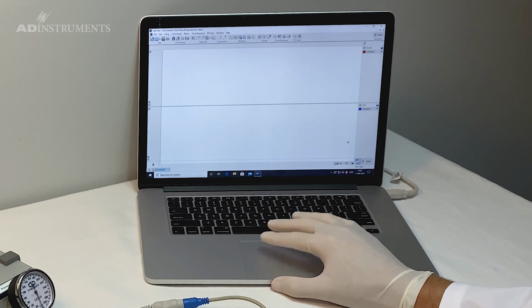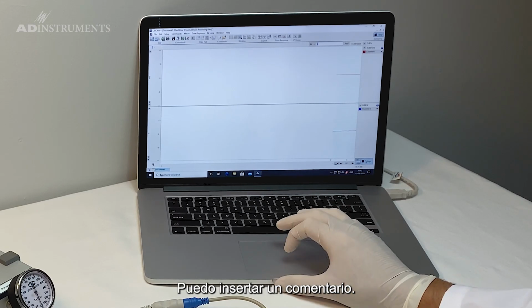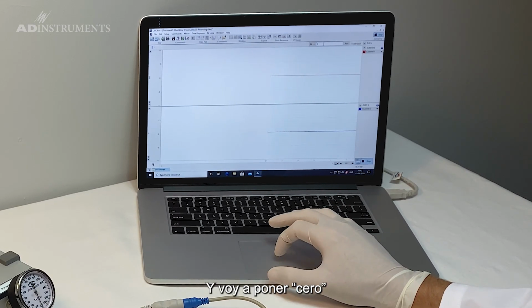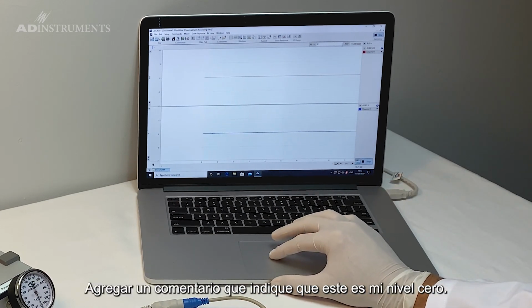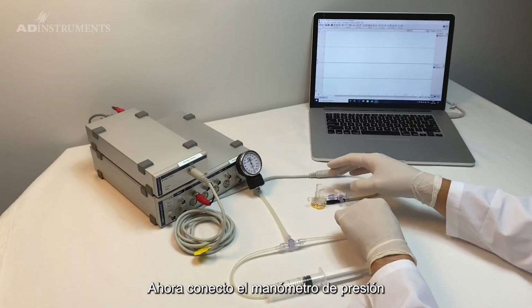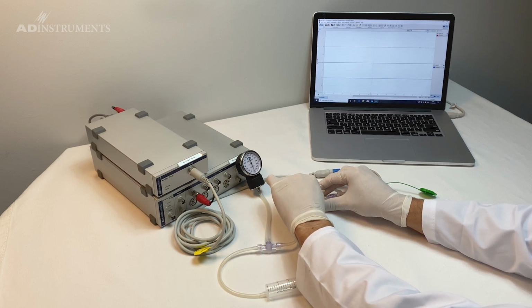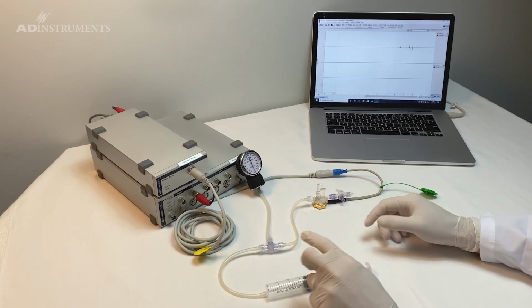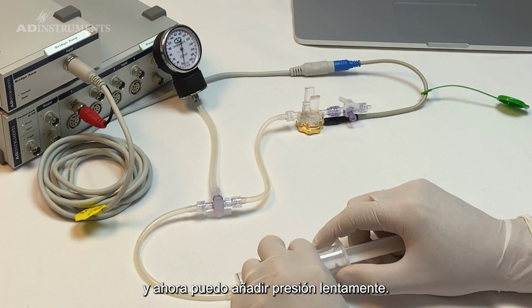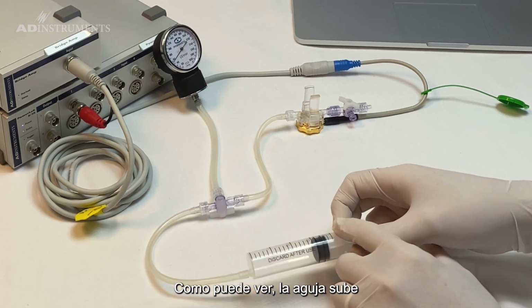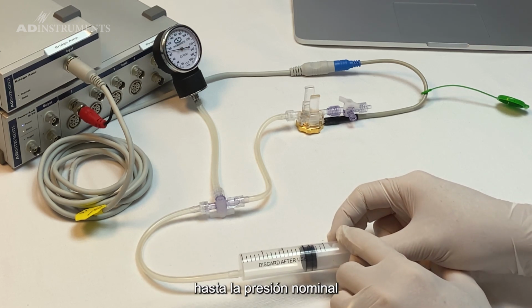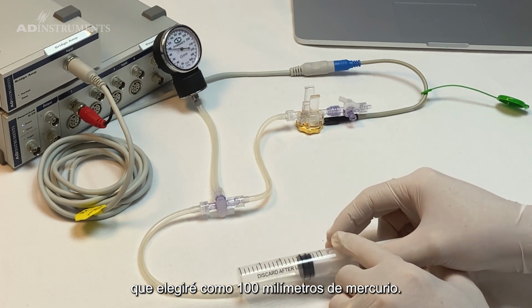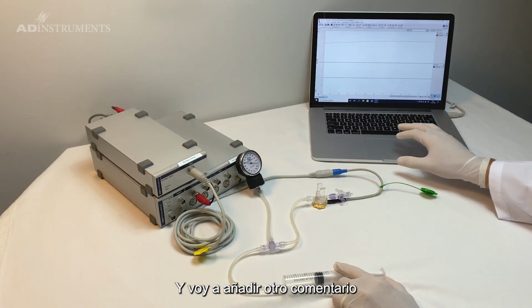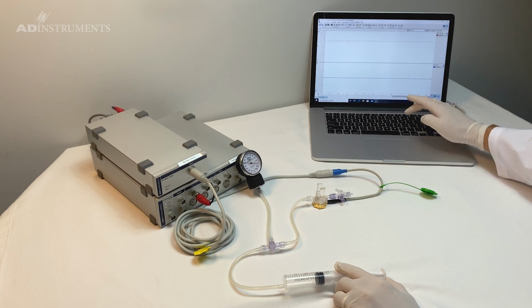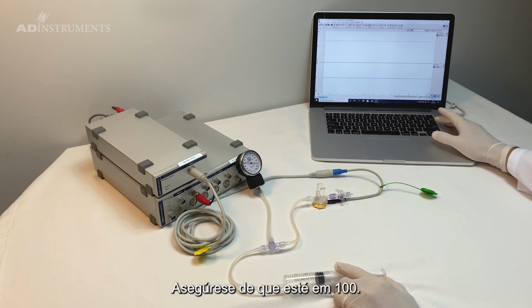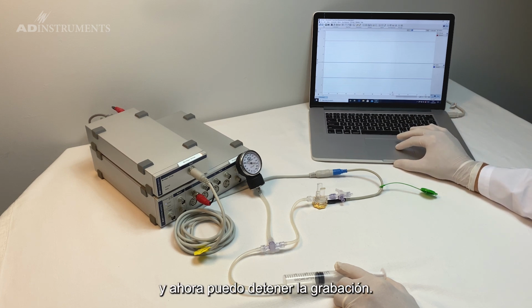So I can start recording, and because it's zeroed and open to air, I can now drop a comment, and I've put in 0, drop in a comment that this is my 0 level. Now I connect the pressure gauge to the other side of the transducer, and now I can slowly add some pressure. As you can see, the dial will go up to my nominal pressure, which I'll choose to be 100 millimeters of mercury. There it is. And I will drop another comment for 100, make sure it's on 100, drop the comment, and now I can stop recording.